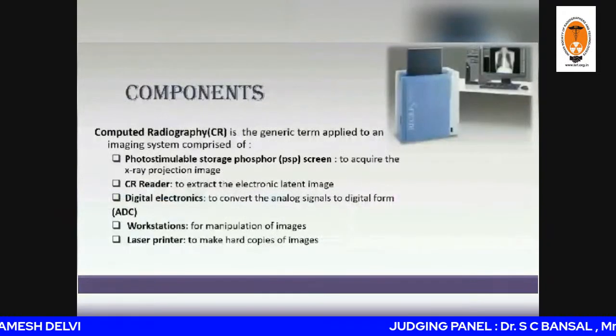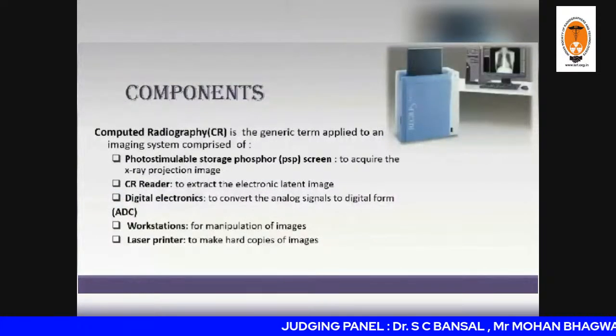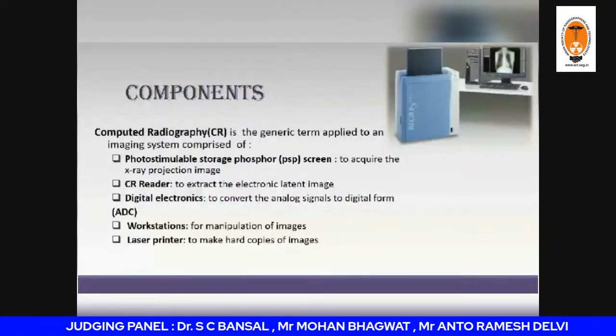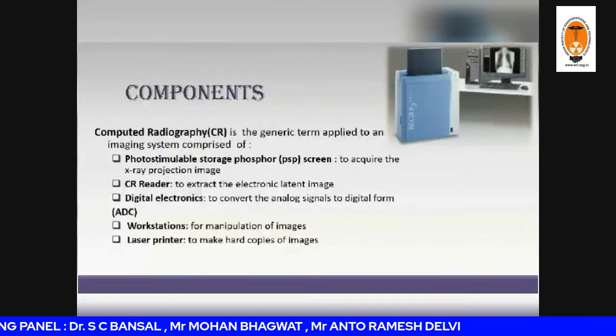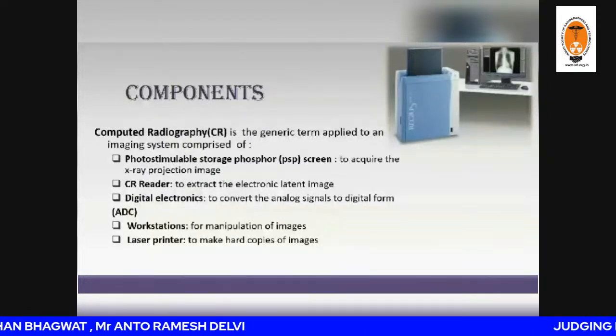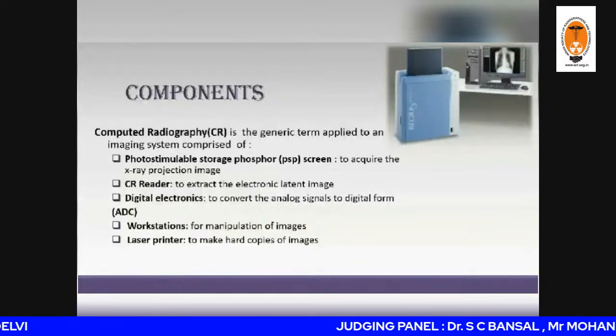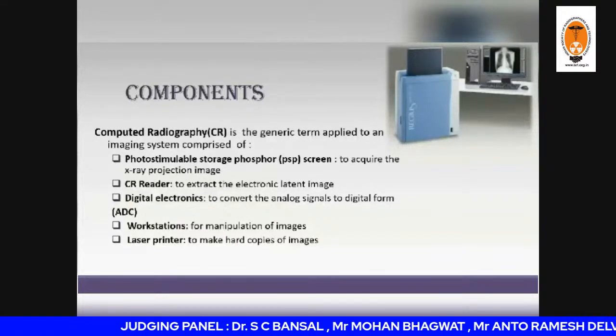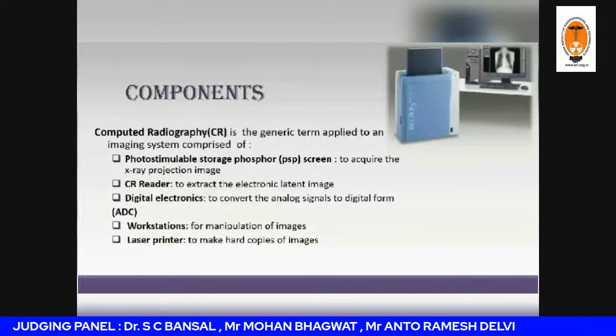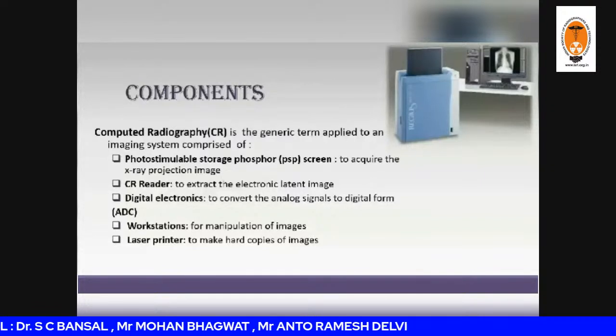Components used in computed radiography. Computed radiography is the generic term applied to an imaging system comprised of photostimulable storage phosphor screens, or PSP screens. The PSP screen is what actually acquires the X-ray projection from the patient. And the CR reader. The CR reader is what extracts the image from this PSP by taking the analog signal and converting it into a digital signal.